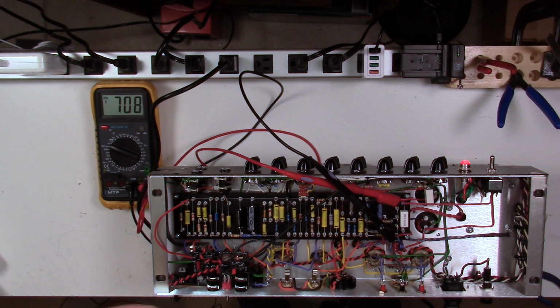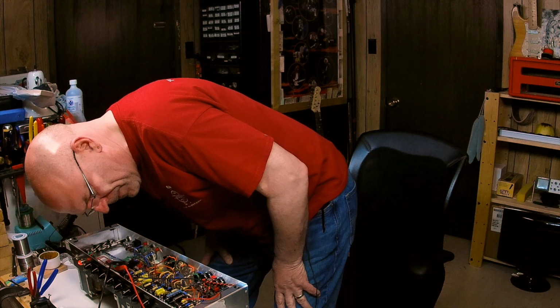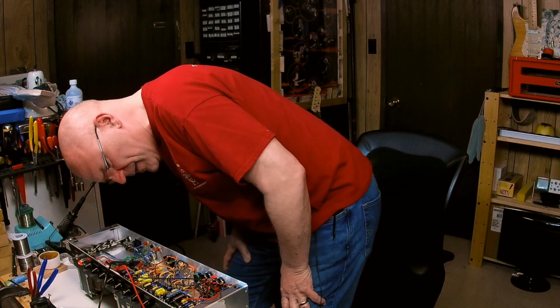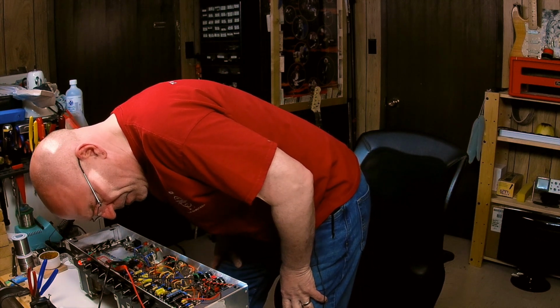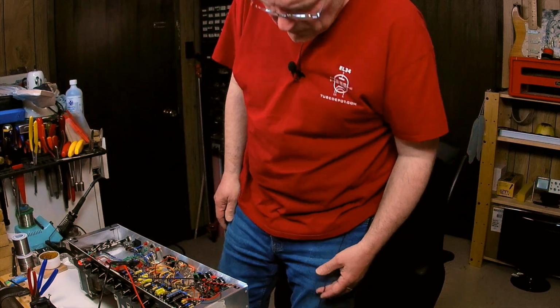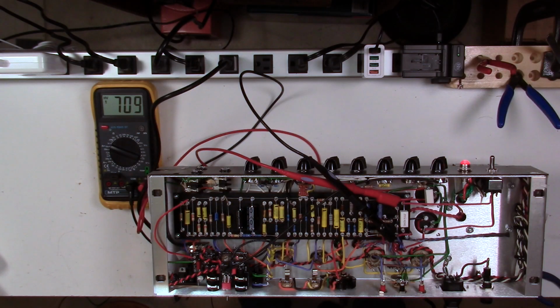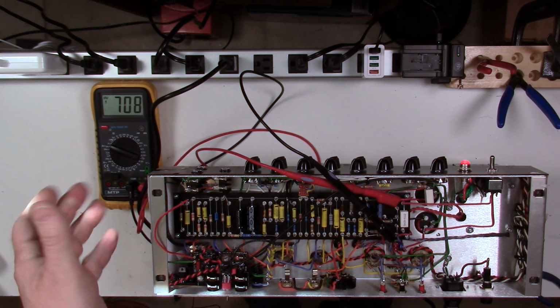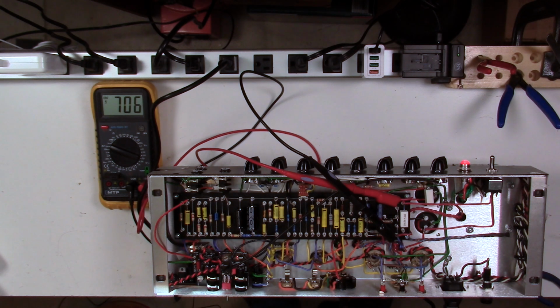It should be at the relay board as well. I can't see, there's an LED on the board under there. I don't want to get my face in too close here. So it's looking good. We've had this sitting here for a minute, 30 seconds. Our voltage is holding steady there, that's of course AC, and everything is looking just ducky.